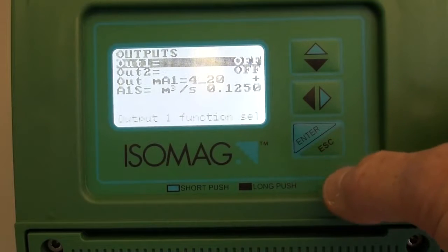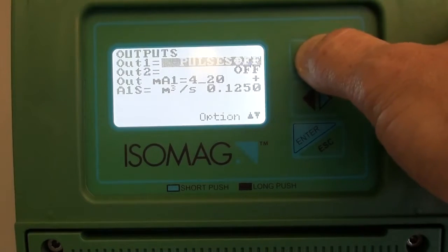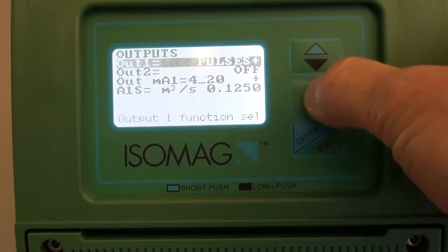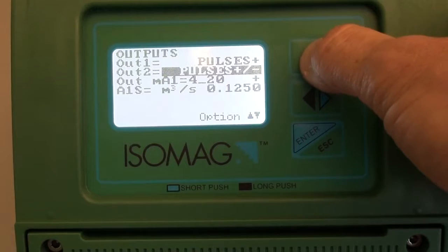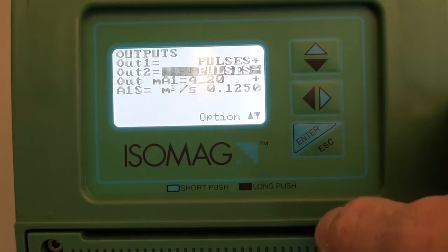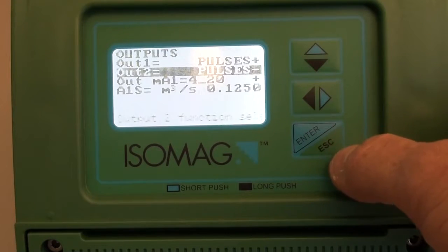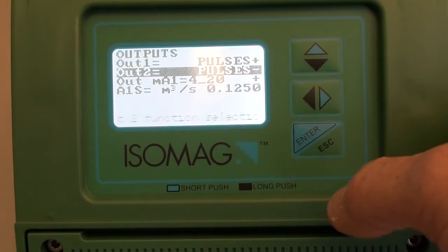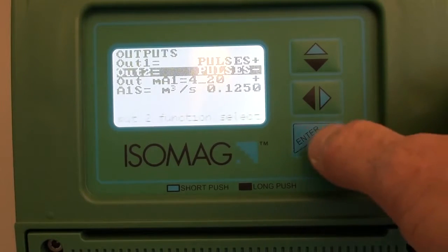So we go to main menu 7, outputs, and select how we want each of the outputs to be set. In this case I am setting each of the outputs to have a function in the positive and negative directions independently. So output one will give pulses when the flow rate is positive, and output two will give pulses when the flow rate is negative.